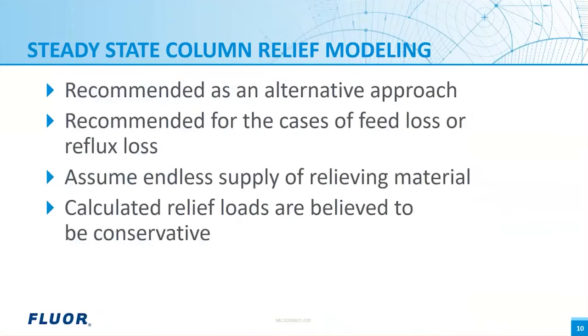As an alternative, steady-state simulation can be used for some cases where the unbalanced heat method does not fit. For example, it is recommended for the vapor blowthrough upset and for loss of feed or loss of reflux cases where a large amount of column liquid holdup is subject to heat input. However, the model does not account for transitional changes or compositional variations during the relieving process, and it assumes endless supply of the relieving material. The steady-state model represents the peak relief moment of the upset event and is considered conservative.